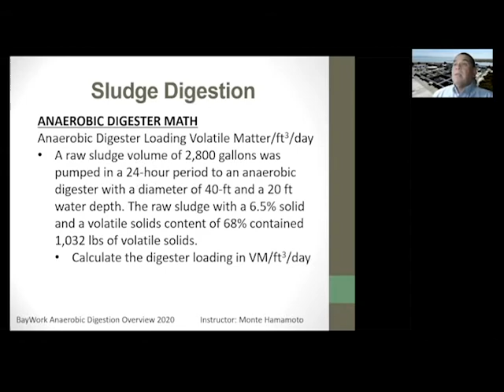We have this many gallons. We know our raw sludge was this percent solid. Calculated that, and we know 68% of that is volatile. So we know we have 1,032 pounds of volatile solids. So we want to calculate the digester loading in volatile matter per cubic foot per day. And we'll find out why this is important to know. So we know this is all the known things that were given to us in the word problem.